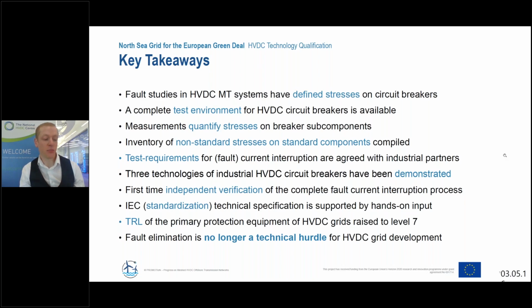And as part of this, the DC breakers are complicated with a lot of standard devices included, but subject to abnormal stresses. So includes vacuum circuit breakers and surge arresters. And as part of the work, we were able to create an inventory of non-standard stresses on these standard components. And all this input allowed for test requirements for fault current interruption to be agreed with industrial partners, giving a common platform and therefore even playing field for these tests.